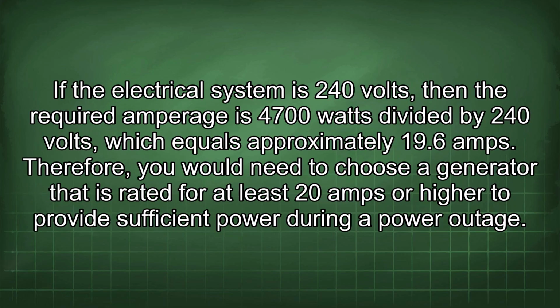If the electrical system is 240 volts, then the required amperage is 4700 watts divided by 240 volts, which equals approximately 19.6 amps. Therefore, you would need to choose a generator that is rated for at least 20 amps or higher to provide sufficient power during a power outage.